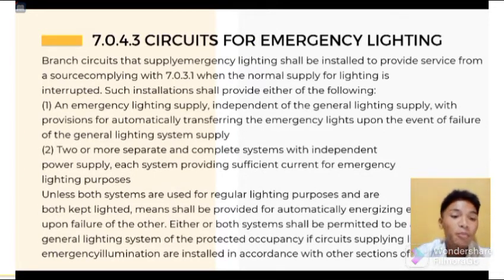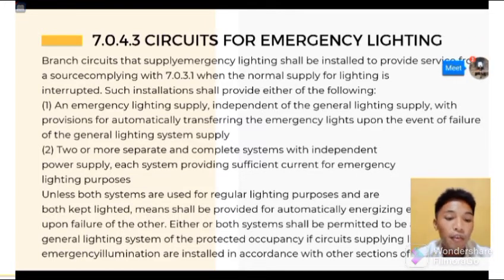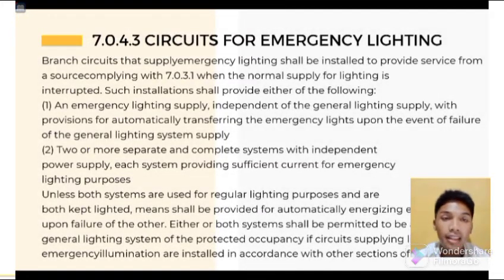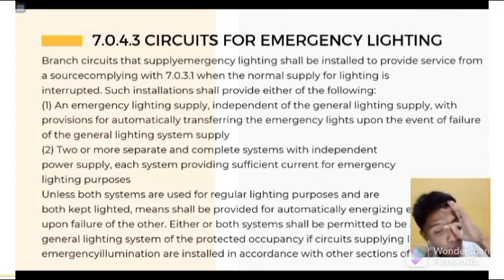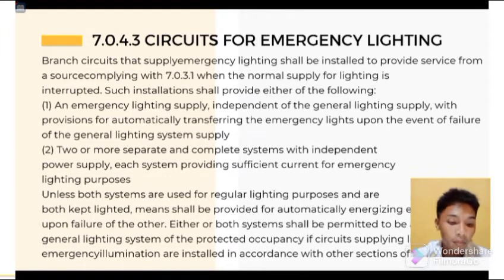Next is the 7.0.4.3, the circuits for emergency lighting. Branch circuits that supply emergency lighting shall be installed to provide service from a source complying with the 7.0.3.1 when the normal supply for lighting is interrupted. Such installations shall provide either of the following. So there are two given. First will be an emergency lighting supply independent of the general lighting supply with provisions for automatically transferring the emergency lights upon the event of failure of the general lighting system supply. Number 2 is two or more separate and complete systems with independent power supply, by which each system provides sufficient current for emergency lighting purposes only.